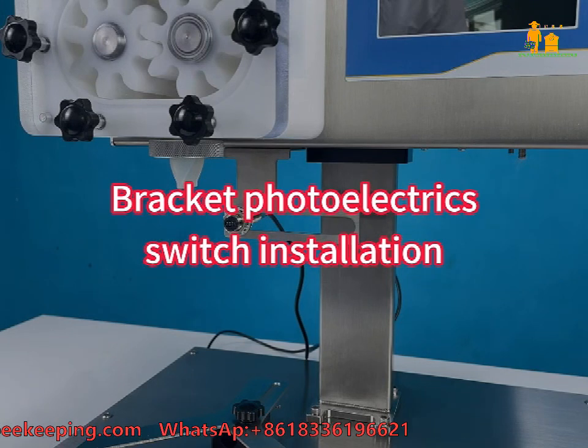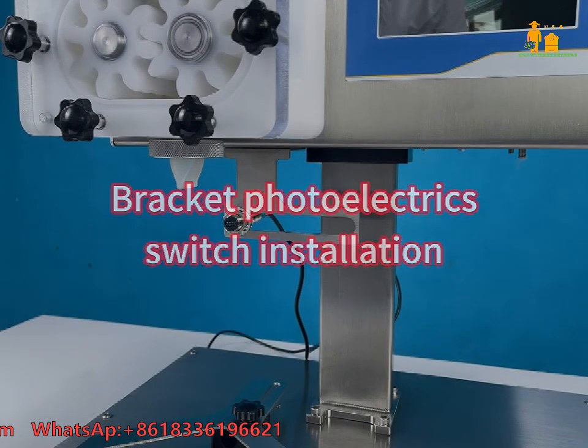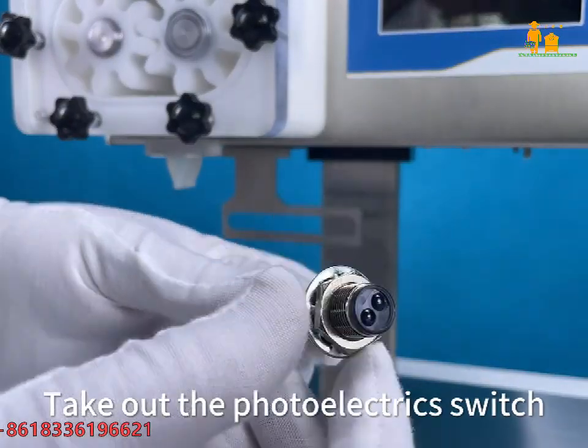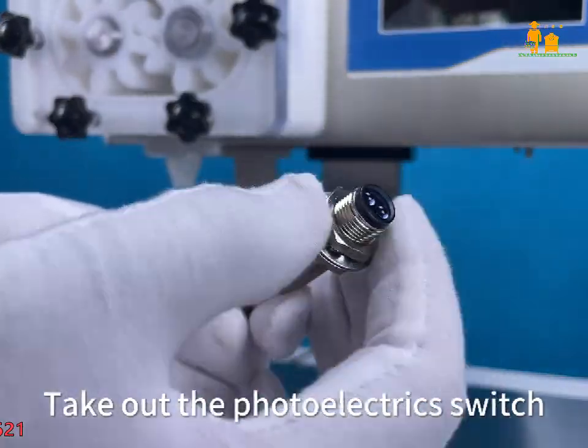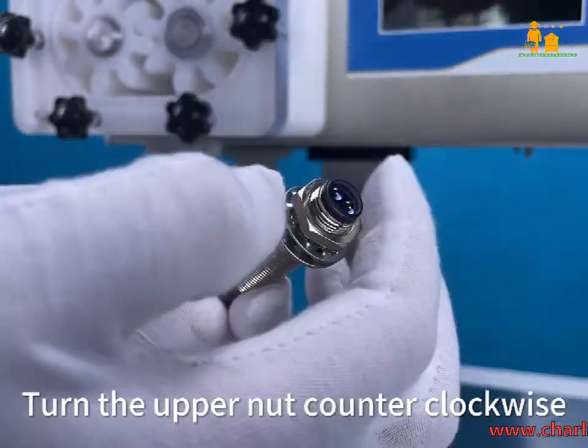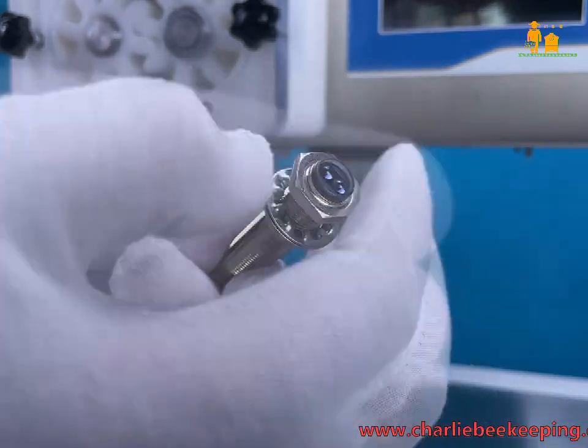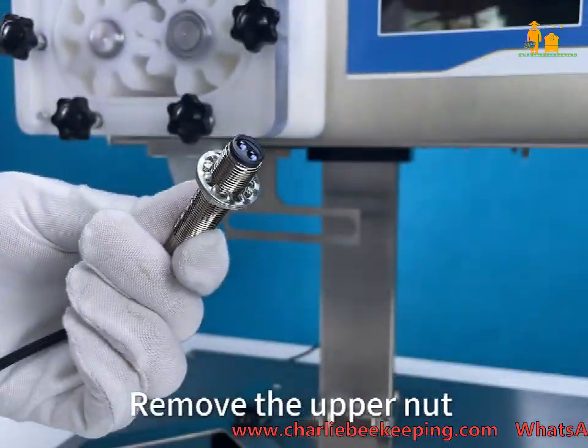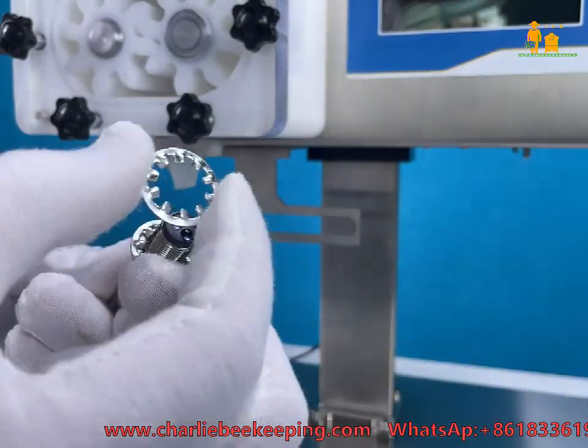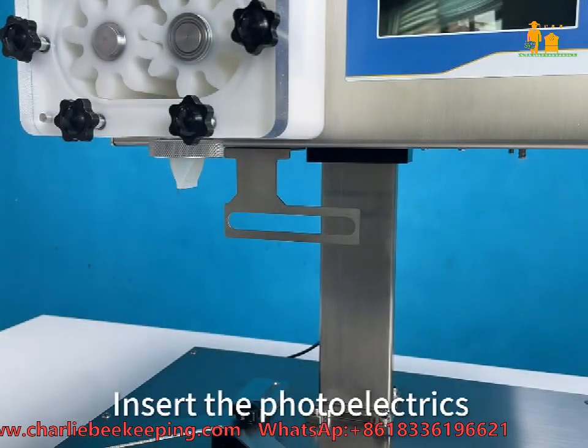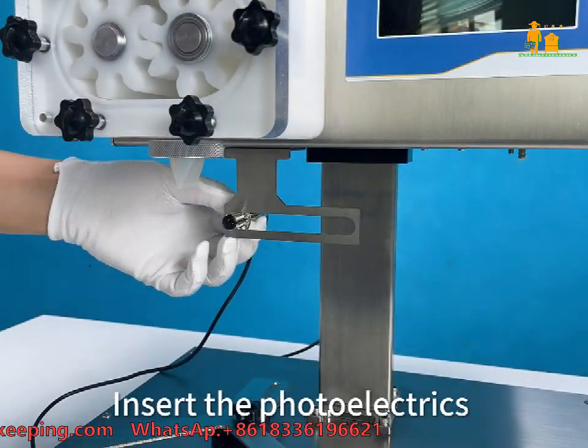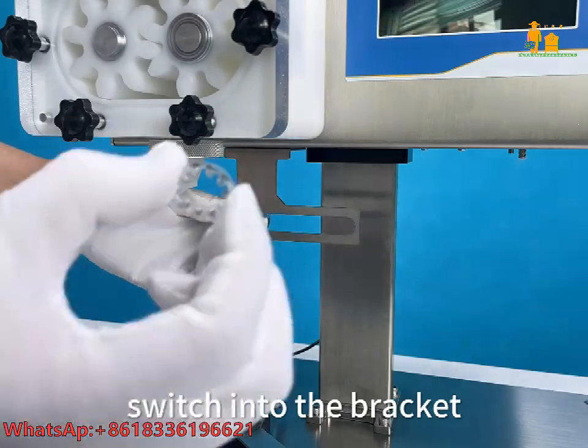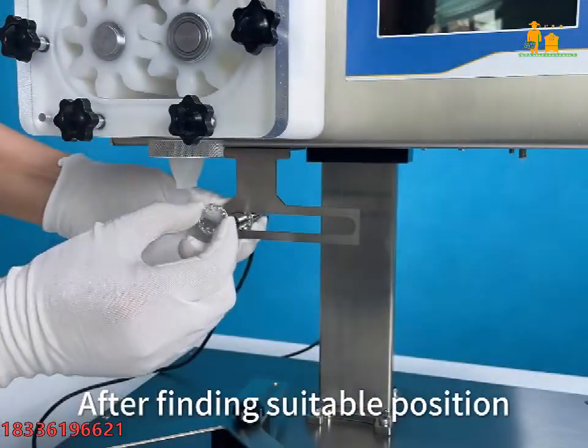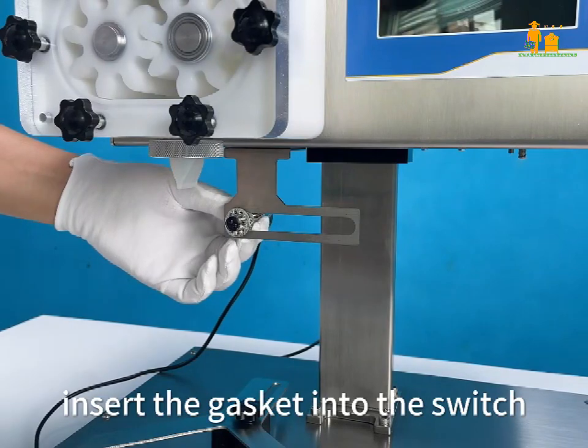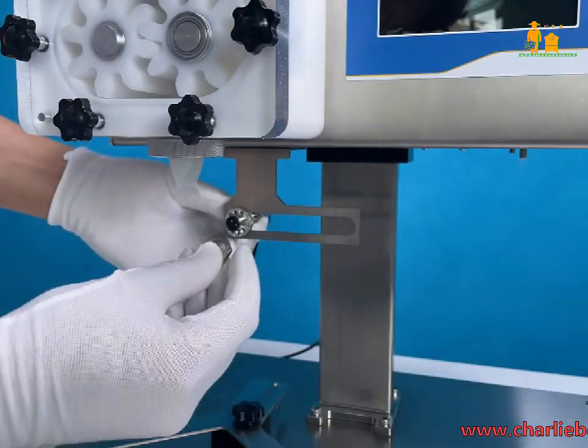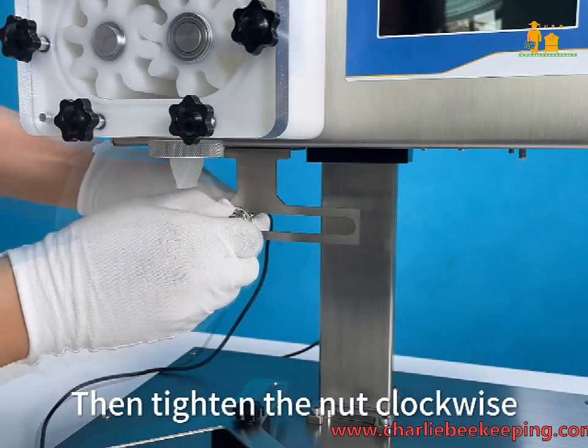Bracket photoelectric switch installation. Take out the photoelectric switch. Turn the upper nut counterclockwise. Remove the upper nut and upper gasket. Insert the photoelectric switch into the bracket. After finding a suitable position, insert the gasket into the switch, then tighten the nut clockwise.